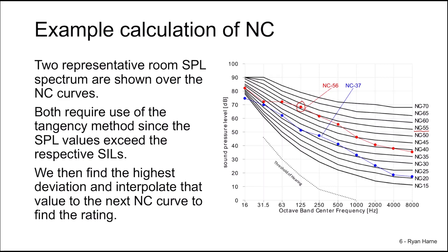Now for the blue data, we see that the highest excess is occurring for NC 35, and it seems to occur at around two places — here and here — by around the same value of two decibels. So we add two decibels to 35, and the NC rating for that room is NC 37.